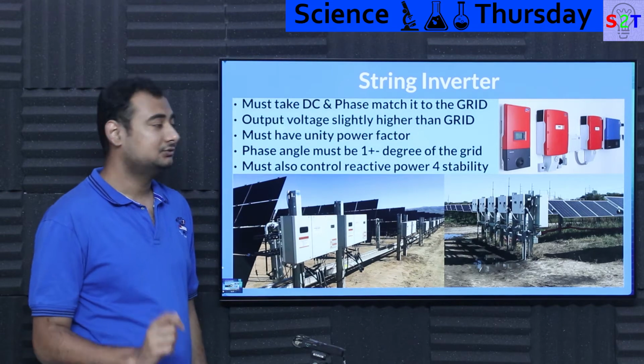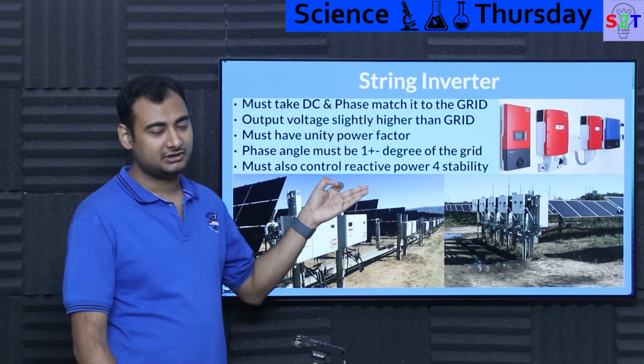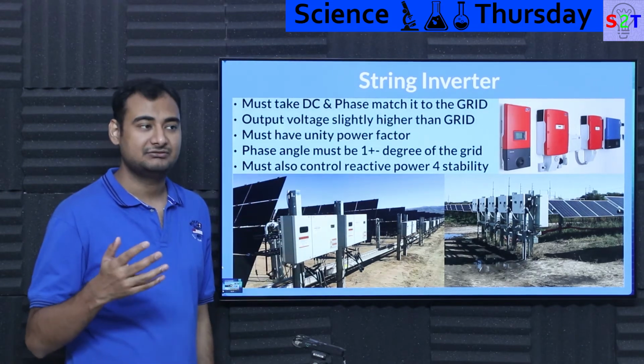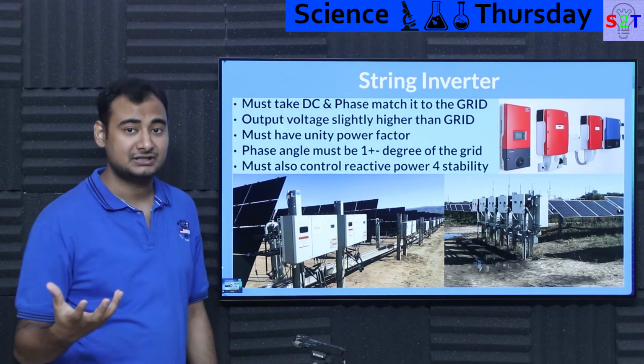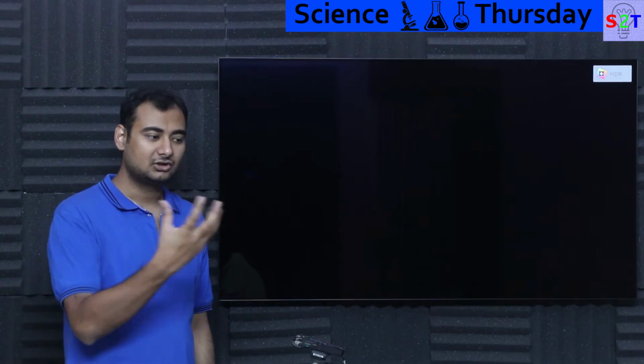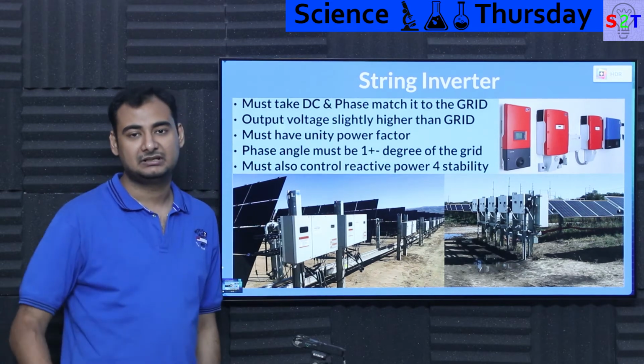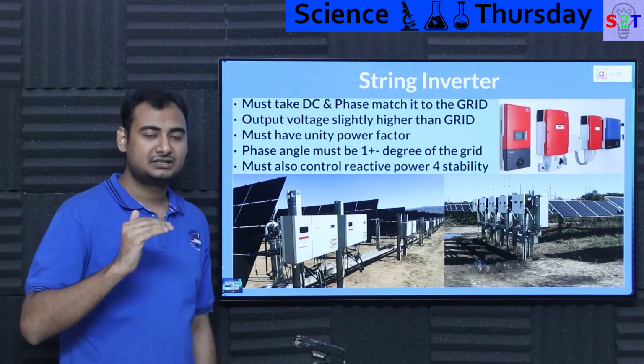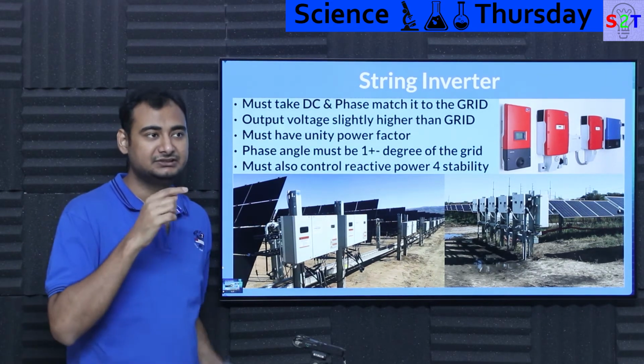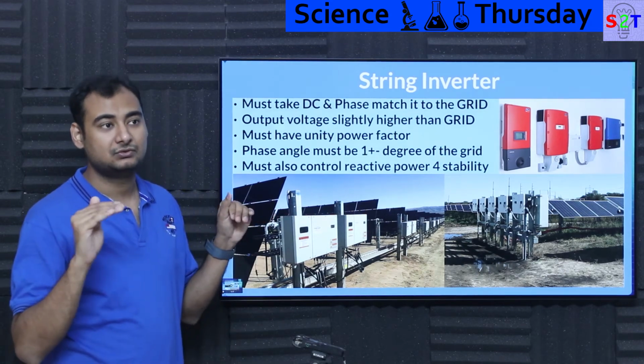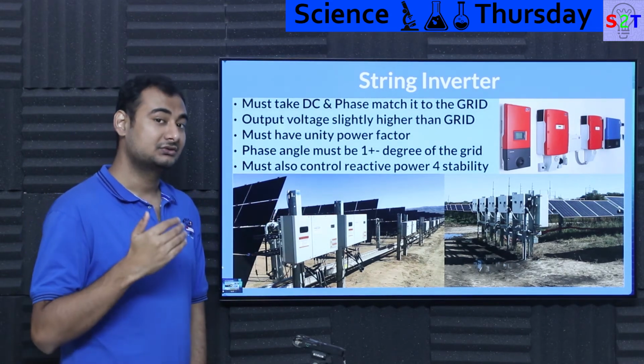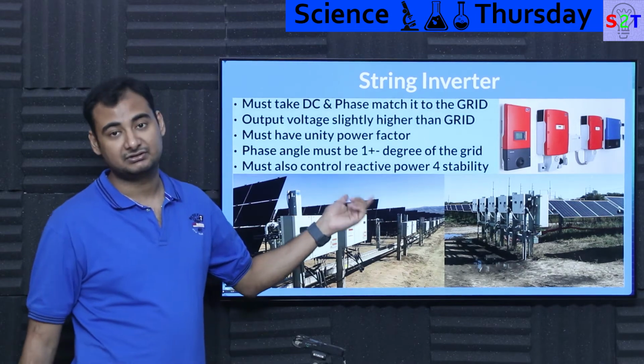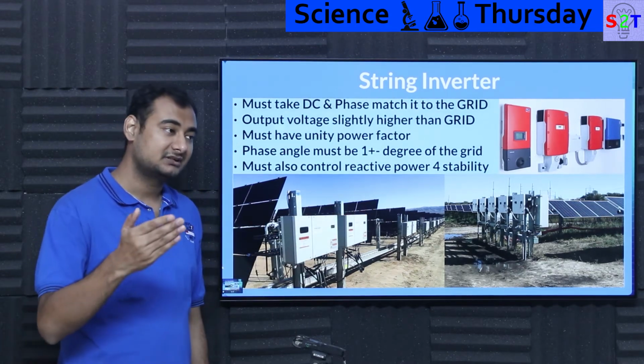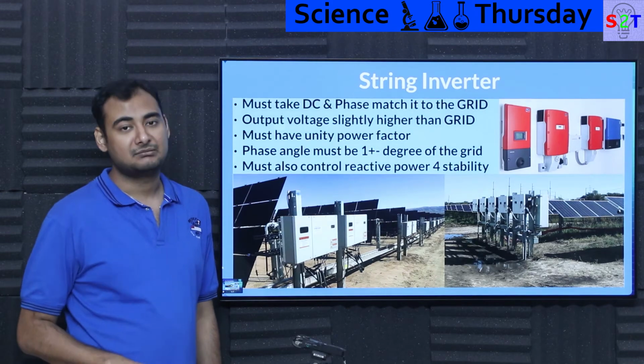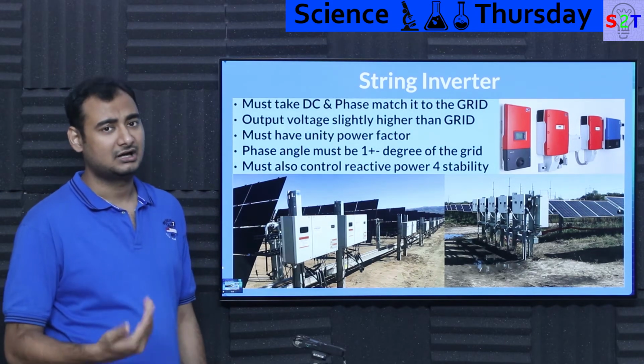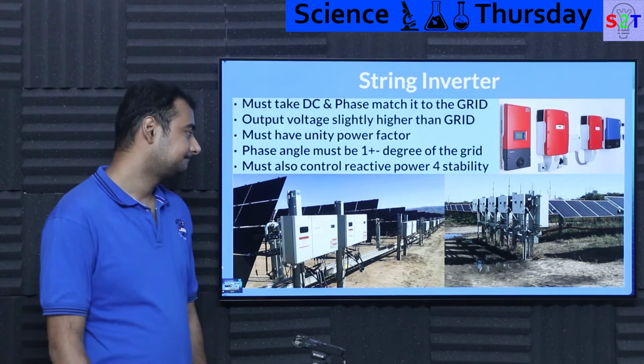And it also needs a way to adjust what is called reactive power. I have provided a video down below. Reactive power needs to be adjusted because if you are living in a scenario, let's say an apartment complex or a lot of small houses, where too many people are using solar during peak time, you could run into a scenario where everybody is feeding electricity, and you will reach a point where overall voltage could reach as high as 300 or 400 volts. So fundamentally you must have what we call reactive power for stability. Reactive power allows them to calm the voltage down. I have provided a video down below on how that is exactly done.